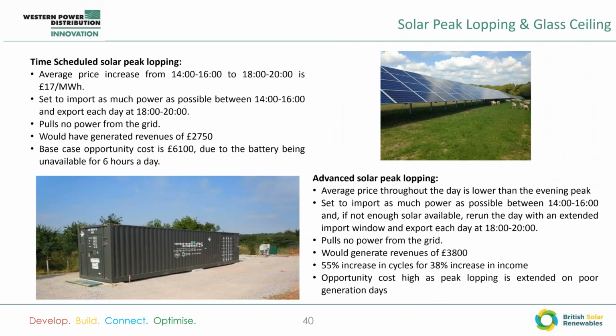So there were 2 types of peak lopping, and I again ran a simulation after doing some real tests. So the average price increase from 2 to 4 p.m. and 6 to 8 p.m. is £17 per megawatt hour. So you get quite a reasonable uplift from shifting the power that would have been exported then and exporting it at the later point.